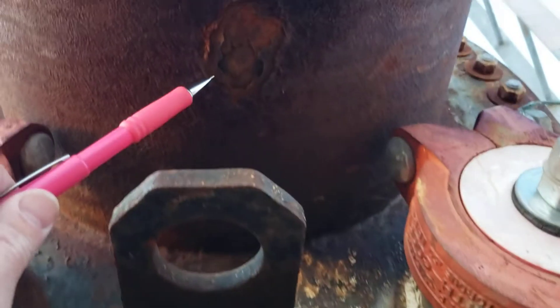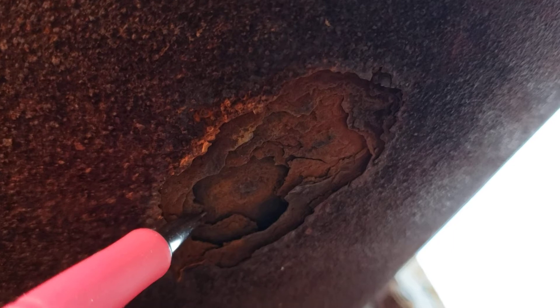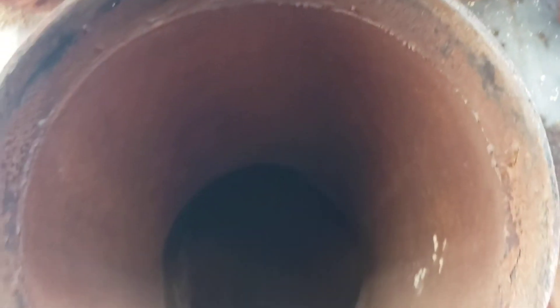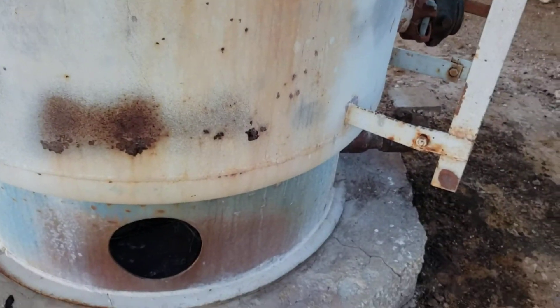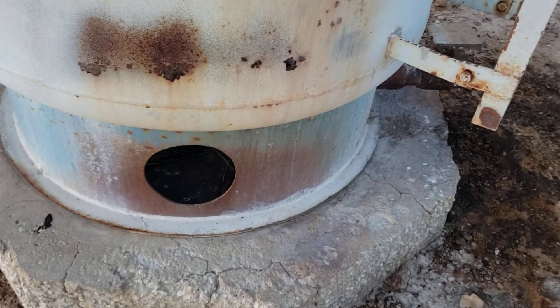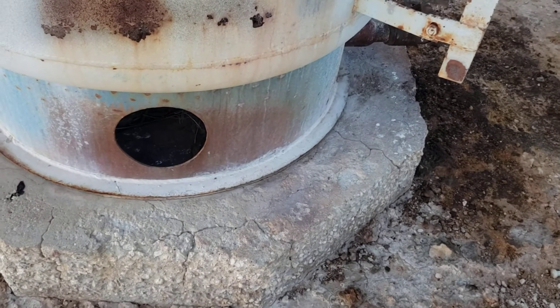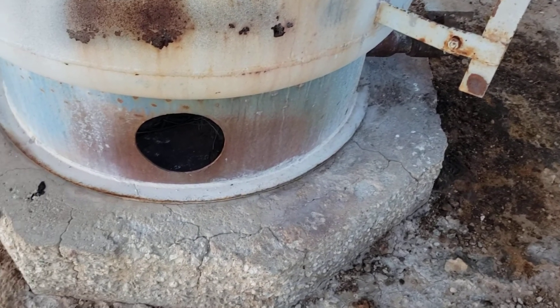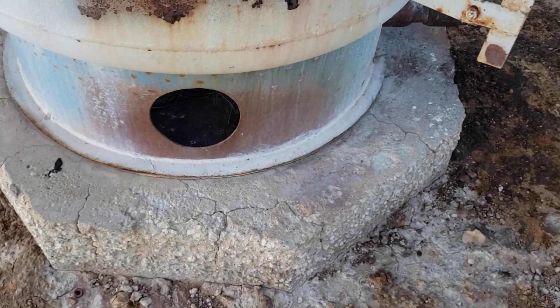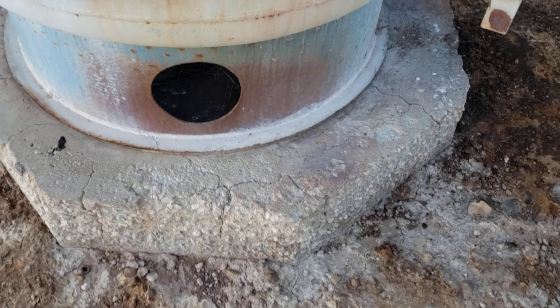This was real common — they just rotted out. I don't know if you guys can really see that corrosion in there. Anyway, that's why these fell out of favor. People realized pretty quick that hey, wait a minute — this isn't about the vertical column, this is about surface area. So horizontal separators are actually much better operating than the verticals.